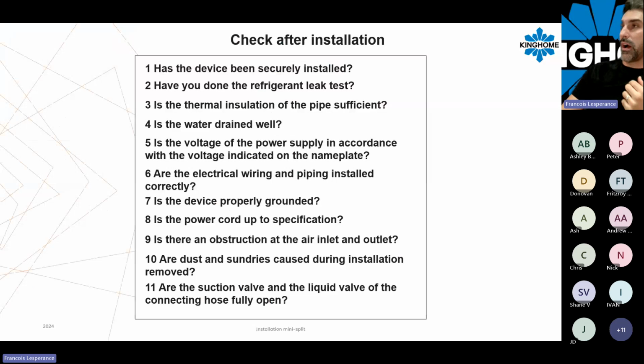So when you have to make a quick check after you have done an installation or a repair on a system and it's time to test it out, take a minute to walk around the unit and make sure everything is securely installed. You have done your proper leak test and vacuum. You have checked the insulation on each pipe, because for a ductless system the liquid line and the suction line always need to be insulated. Make sure you don't have a gap in your insulation that can cause condensation and leaks. You have tested the drain as well, and everything is okay.